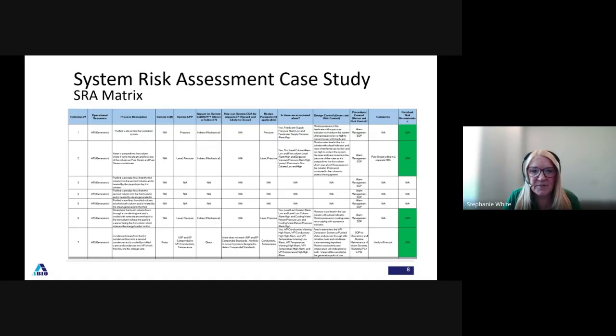And then the next column, how can the system CQA be impacted? Well, it's not impacted because there isn't one at this point in the process. So it's NA. And then the recipe parameter that we're going to be monitoring is pressure, because from a mechanical standpoint, pressure is important going into the system. And is there an associated alarm? There were associated alarms with pressure, but they're not critical alarms.